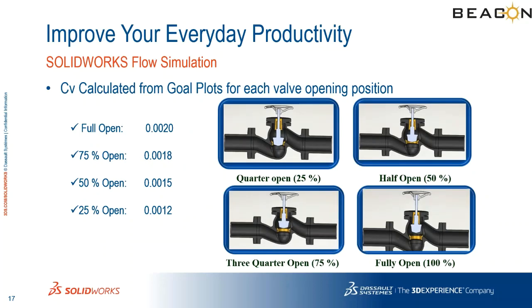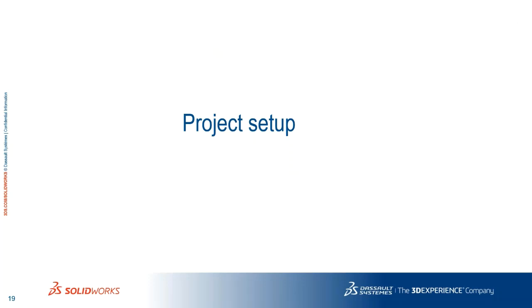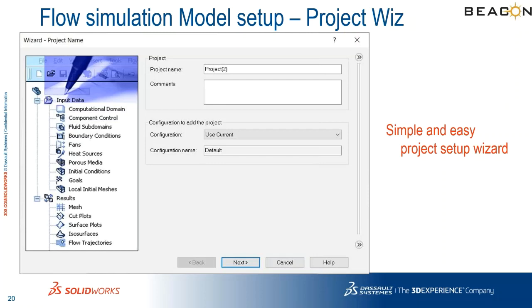The different opening conditions are 25%, 50%, 75%, and 100% open. We'll set up a study for one of those. The quarter-open, half-open, and fully-open positions are shown. The essential entity to calculate for Cv is the pressure drop — that is the objective of this study. It is very easy to set up using the project wizard, which I'll show first on the slides and then in a live SOLIDWORKS demonstration.